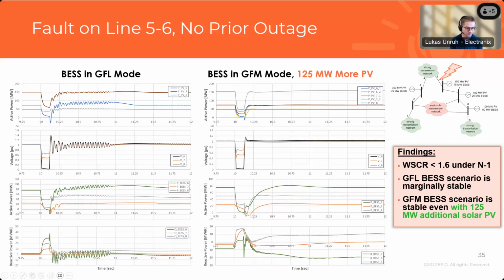So there's a pretty large voltage transient at fault clearing, and then pretty heavy oscillations for about a second before things stabilize. And when we model those batteries as grid forming, we actually get a stable result for the base scenario. And then to quantify the benefit here, we added an additional 125 megawatts of grid following PV into this corridor, and we found that was stable. So this is an example where we unlocked more grid capacity for IBRs along this corridor.